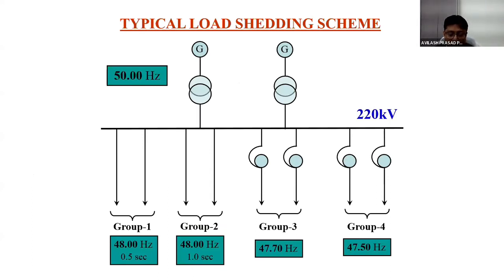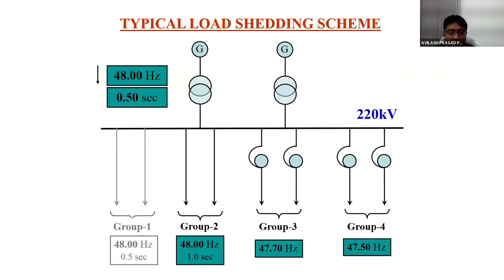if there is a 50 Hz generation and suddenly frequency falls to 49.6, you can see group 1 is at 48 Hz. If frequency falls to 48 Hz and the time elapsed is 0.5 second, then group 1 gets shed. Now time is 0, 0.1, 0.2, 0.3, 0.5. Then automatically group 1 gets shed. The load connected with group 1 gets shed. So accordingly we do the logistics of which load can be shed if this type of situation occurs.